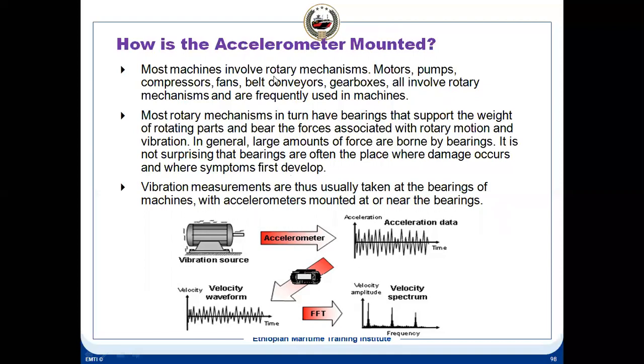Motors, pumps, compressors, fans, belts, gearboxes. You see many gearboxes. You'll find these sensors, these accelerometers, installed everywhere. Most rotary mechanisms in turn also have bearings. In the bearing you'll also find this, which supports the weight of the rotating parts and bears the forces associated with the rotary motions. So you'll find these sensors placed everywhere. And these sensors will give the signal.